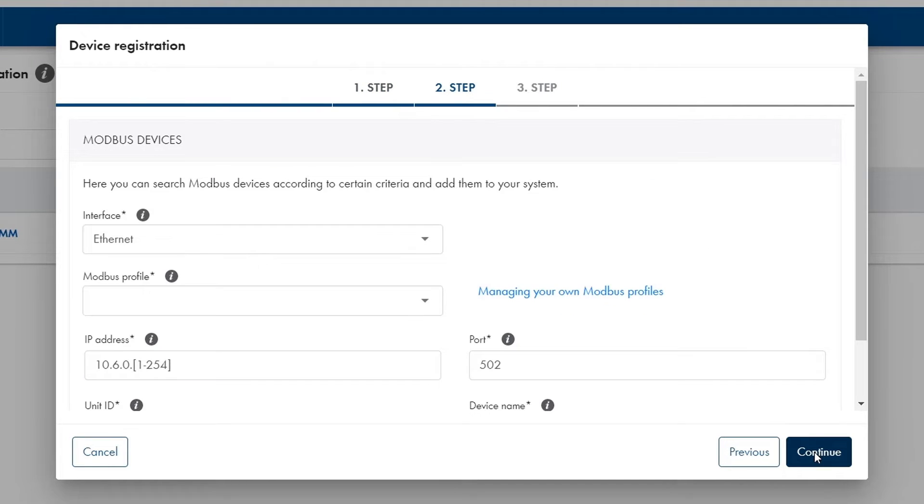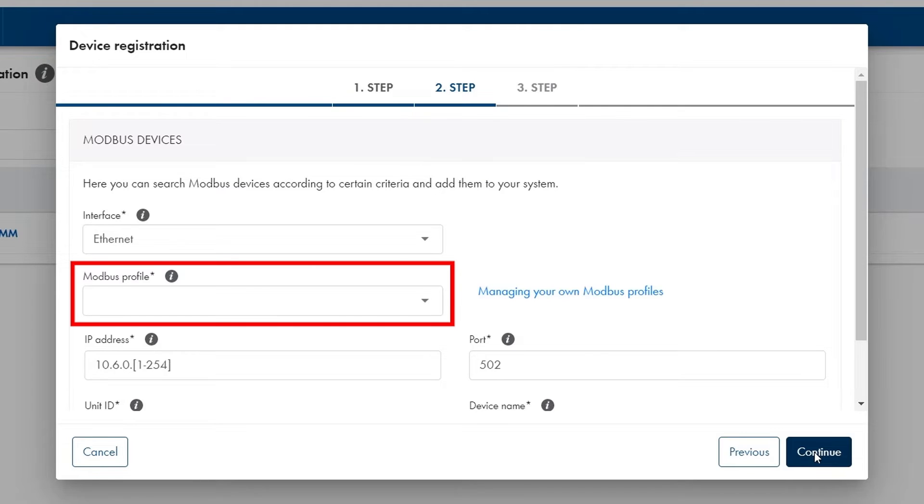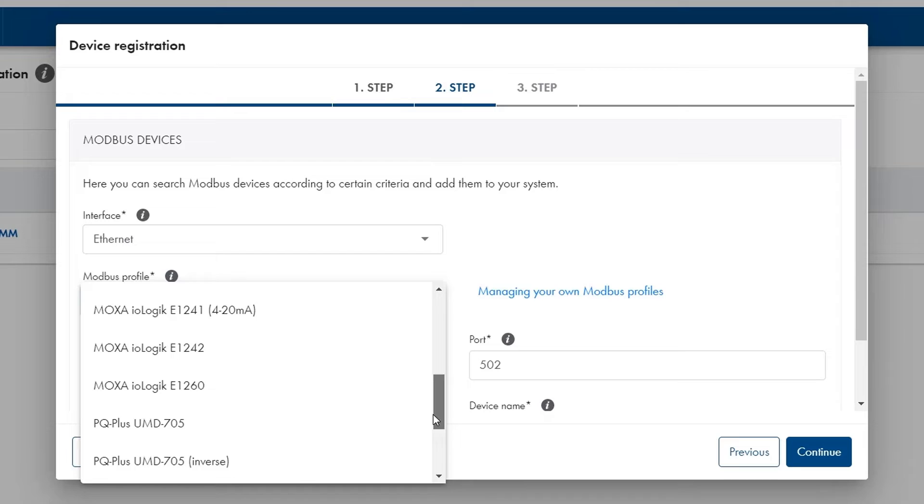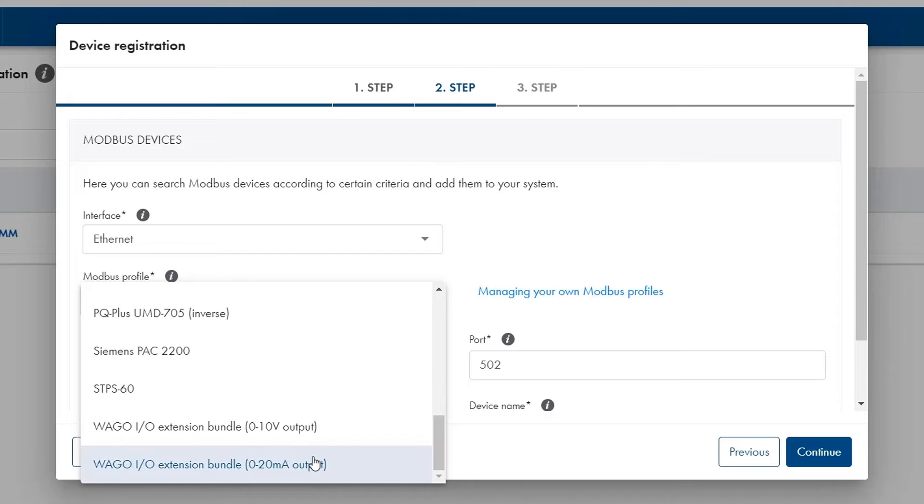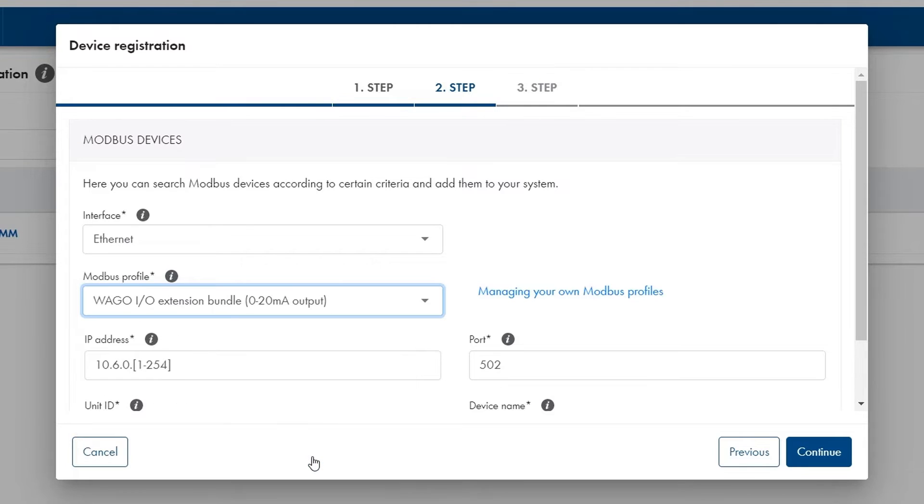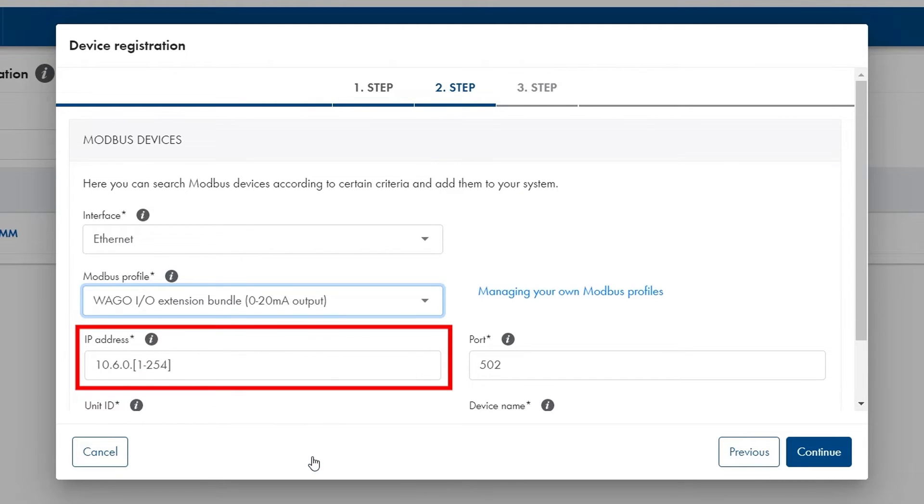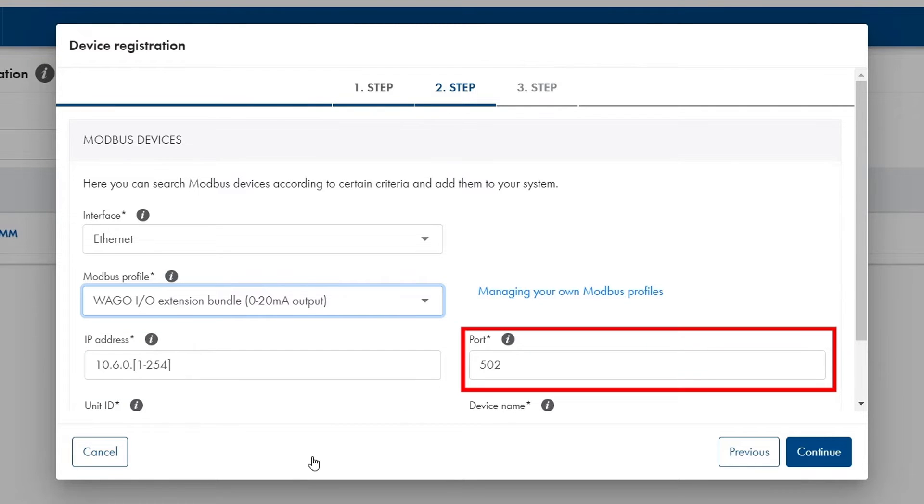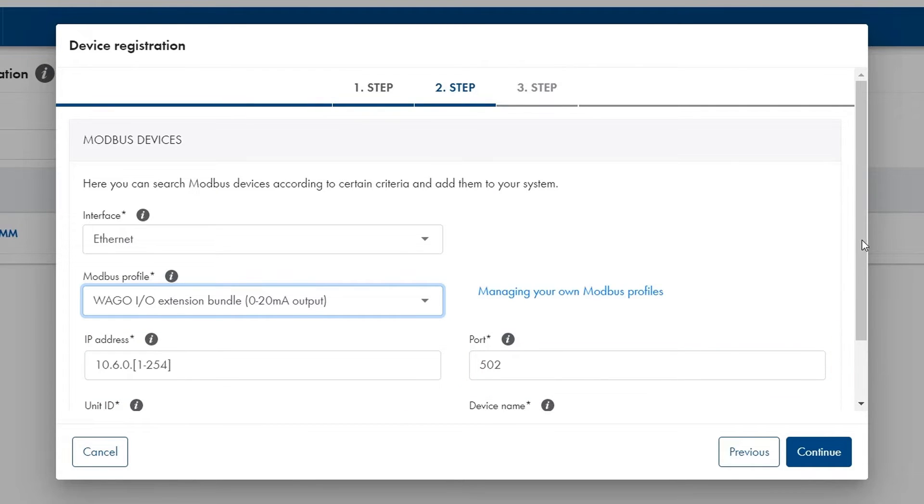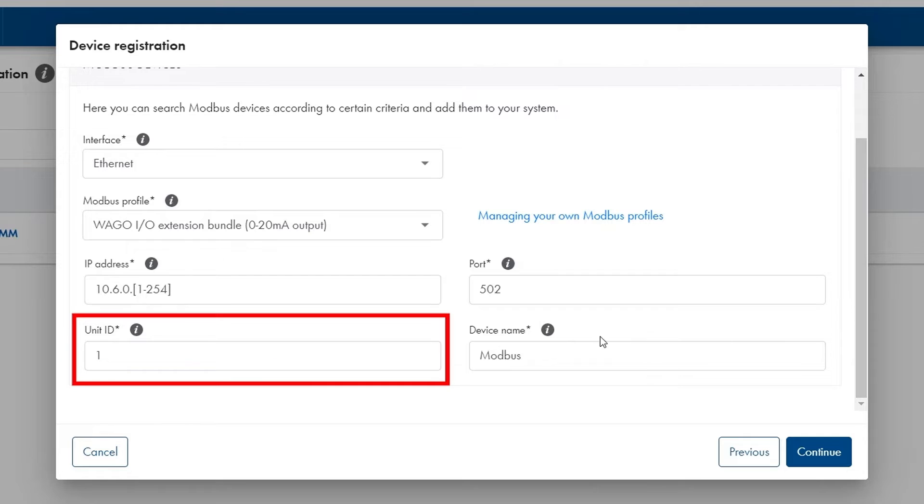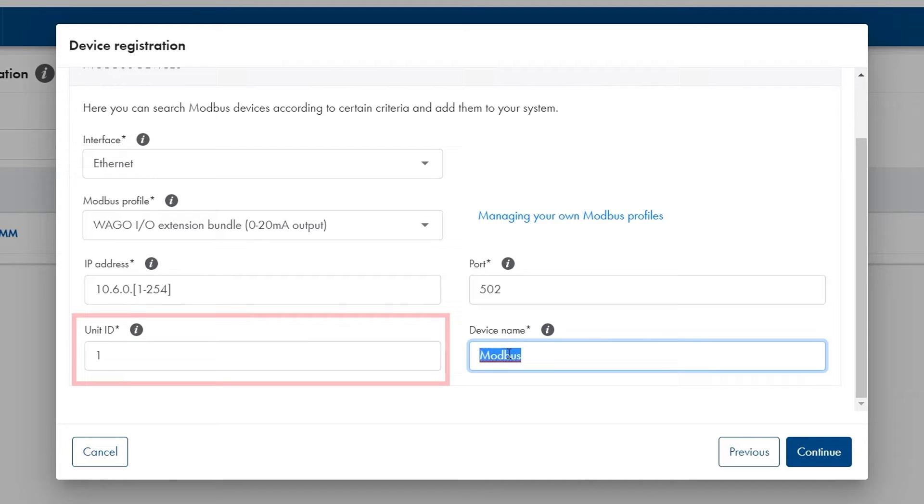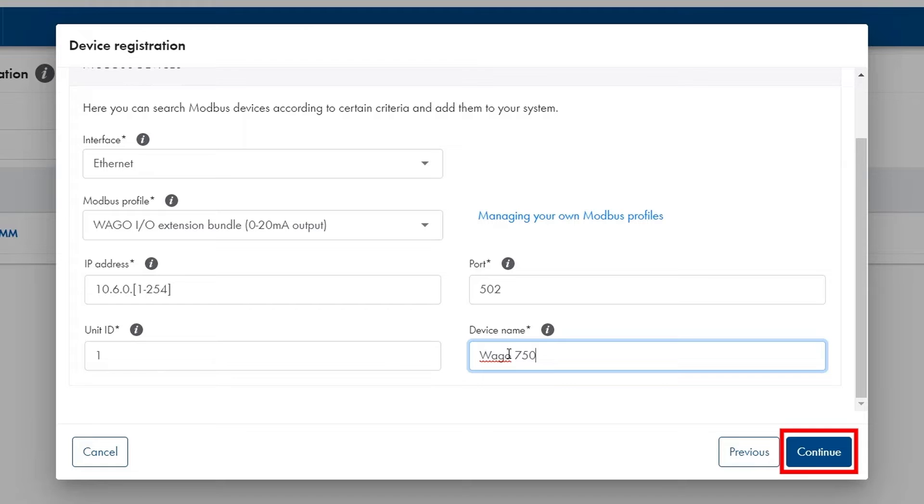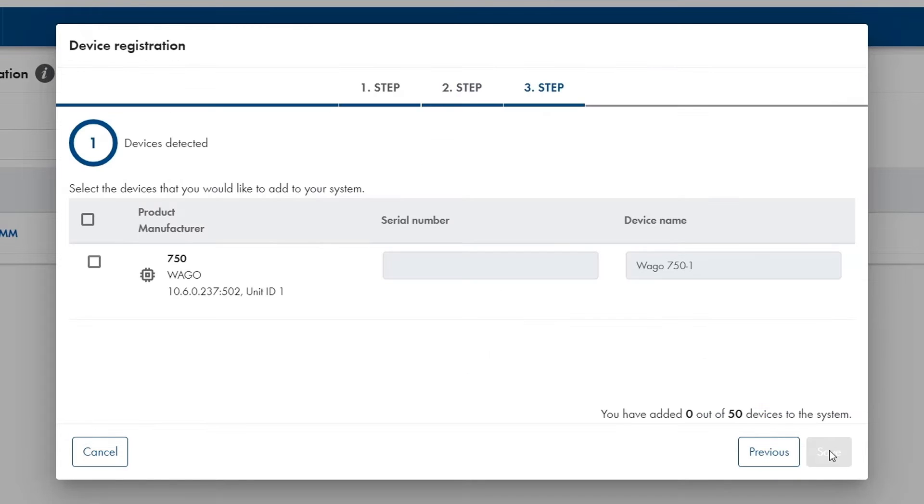Then a new window is opened where I should set which kind of Modbus device I have. I choose the WAGO I/O extension bundle 0 to 20 milliamp output. I can also choose the IP address of this device. For standard Modbus devices the default port is 502 and the default unit ID is 1. But the device name can be adjusted. Once I'm done with this setup I click on continue.